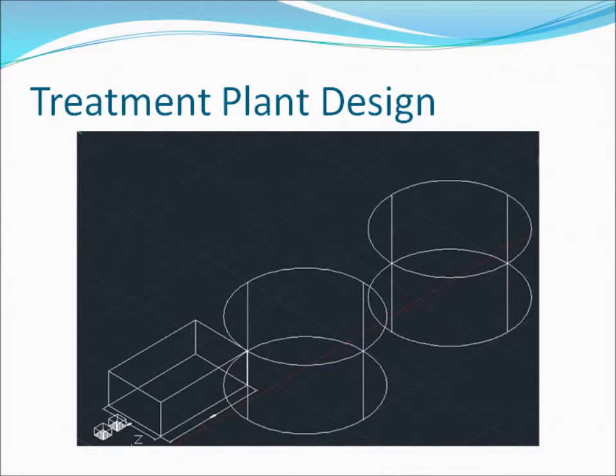Once the gray water reaches the treatment step, it will come into contact with 2 microfilters that will filter out particles around 5 microns in size. Next, the gray water needs to be disinfected. It will go into our disinfection tank, which has surface dimensions of 15 feet by 9 feet and a depth of 5 feet. Chlorine will disinfect the water, and it will also serve as an odor control for the treatment plant. There will be a hydraulic residence time of 30 minutes in the disinfection tank.